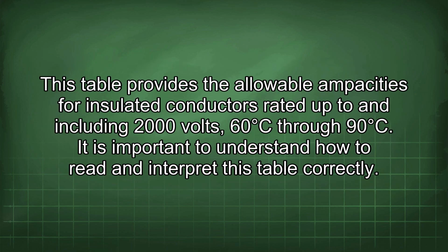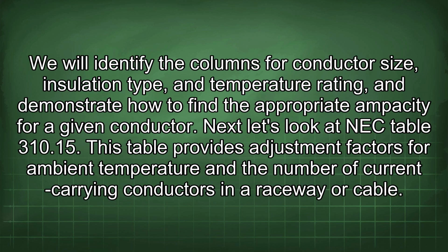This table provides the allowable ampacities for insulated conductors rated up to and including 2000 volts, 60 degrees C through 90 degrees C. It is important to understand how to read and interpret this table correctly. We will identify the columns for conductor size, insulation type, and temperature rating and demonstrate how to find the appropriate ampacity for a given conductor.